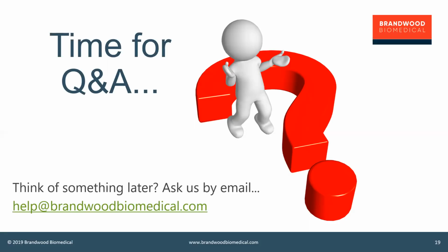Is it still the EP checklist or is it the GSPR? Yeah, again, I think he means ER checklist, because we're talking about Europe here in the MDR, but the EP checklist is not going to change for Australia. I don't think there's any consideration on that. But as the MDR has been implemented, there is a movement to this GSPR conversation.